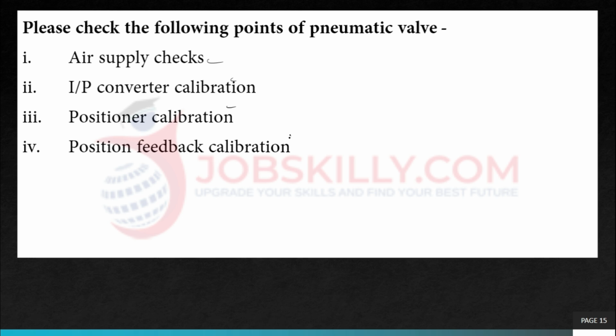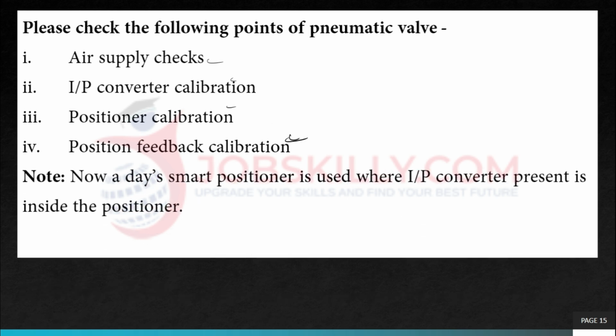Position feedback calibration. Sometimes the I to P converter is present inside the positioner. Now a new type of control valve is coming where we have only one positioner. We have to do the setting on that.